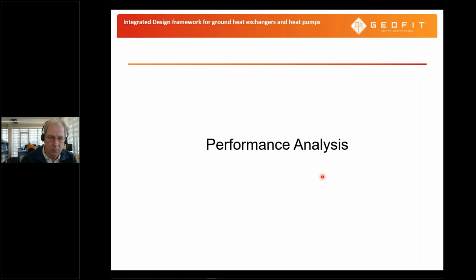So I think we've shown now that the analytical solution gives a pretty good solution of the performance of an earth basket type heat exchanger, and obviously the vertical borehole and slinky type heat exchangers have been validated as well against other existing software.